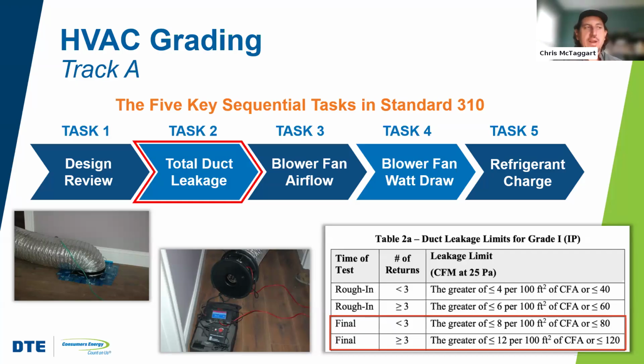I'd say colloquially within the rater community, we tend to speak more in the narrative of percent of floor area rather than saying the entire mouthful of leakage per 100 square feet of conditioned floor area served, it's just more of a mouthful. So it's a lot easier to say 12% leakage, 8% leakage, 4% leakage, etc. But they mean the same thing ultimately. Thank goodness we don't have to hit literally 12 CFM for the whole house, because no house would ever be an Energy Star home, because getting to those exquisite levels of almost zero leakage are practically impossible.